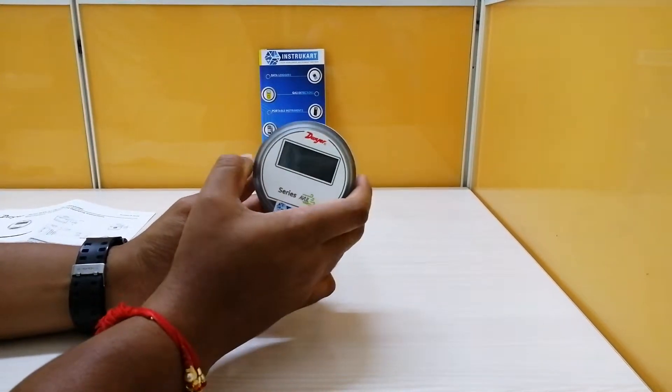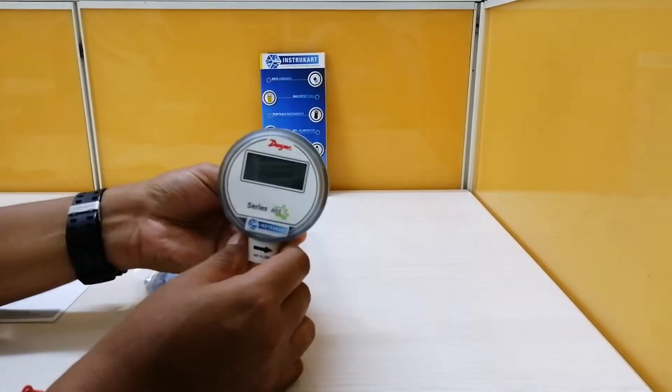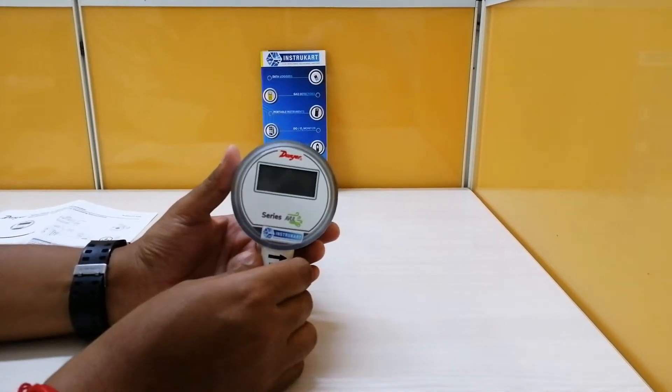This has a temperature limit of 0 to 50 degrees. To plug into and excite this sensor, you have to use 24 volt DC power supply with a tolerance of plus or minus 20%.